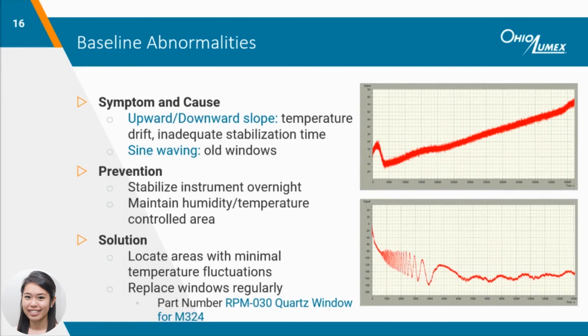We recommend a minimum warm-up time of 2 hours, but the baseline is really the best indicator of instrument stabilization. Each instrument varies a little bit, so longer stabilization time may be necessary if the baseline hasn't settled out after a couple hours. If possible, setting up the instrument to warm up overnight is optimal.